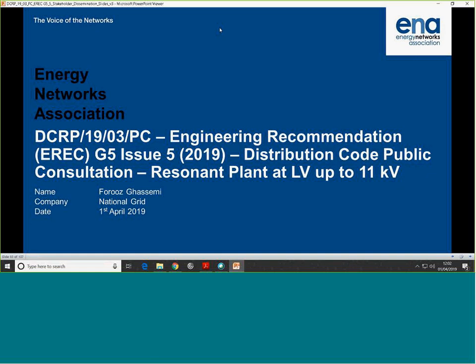Cheers. Thank you, Vincent. This is a new section in G5. The reason for this section is, as I mentioned earlier on, there are lots of incidents where capacitor banks at LV and 11 kV explode because of harmonic stress. And also when people have cables or are putting new cables in their installation, it may change the background profile, amplify some harmonics, reduce some others. So basically capacitors and cables like capacitors have an impact on the background harmonic level.